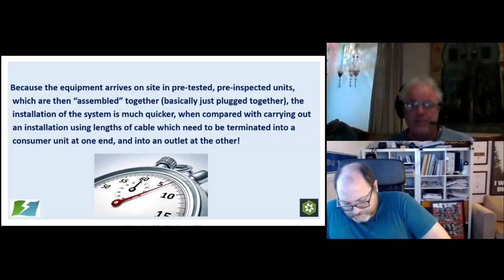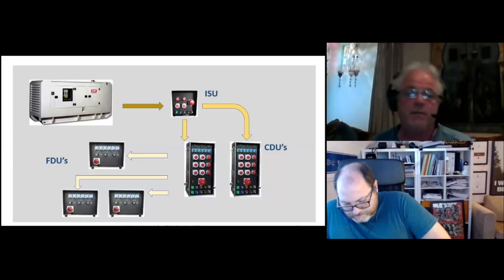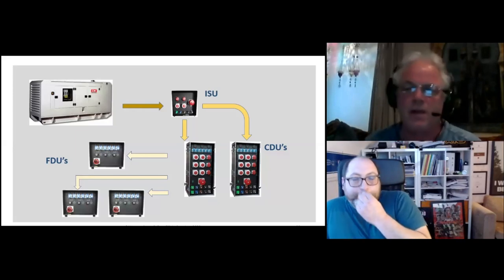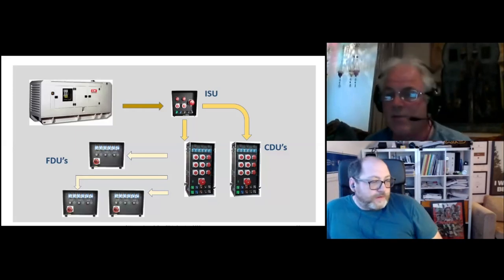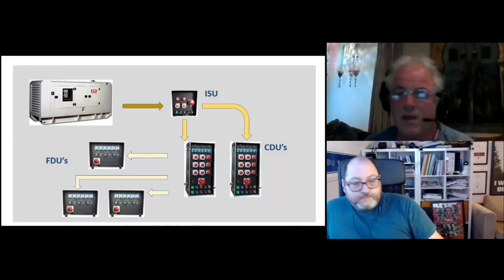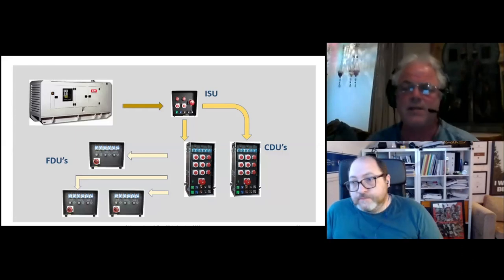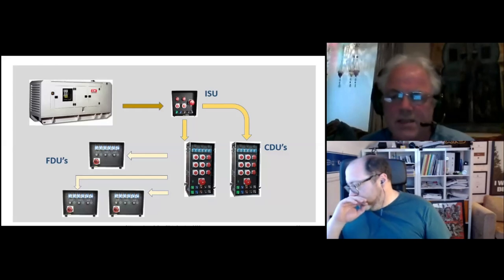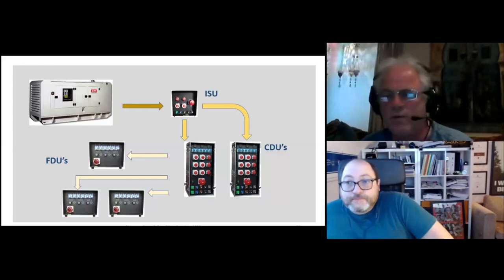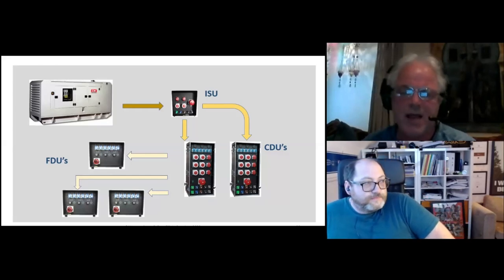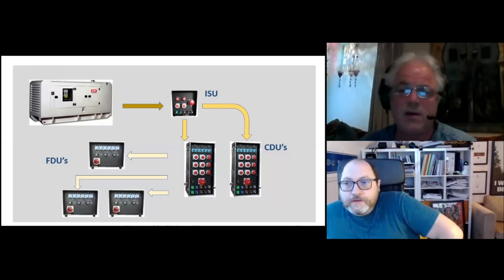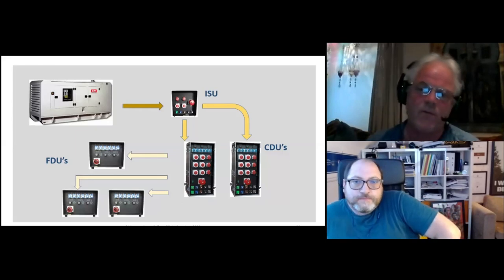So we end up with a system which is possibly similar to this. You'll have a generator feeding an ISU. Your ISU may feed a number of CDUs, and the CDUs may feed a number of FDUs. You might just come off the generator straight to a CDU, and that might be all you need. So there's no strict design to this. There's no strict, oh, you must use this, you must use that. You use what you need to use, and you remain flexible, you remain dynamic.